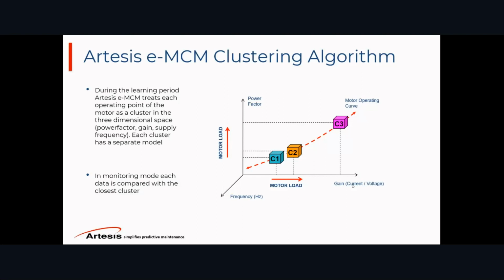If it's not an issue, and if it's a seasonal or intentional change in the system behavior, you can then update this model by just updating the software, and it will create additional clusters for that particular condition. That way you always ensure that all conditions are learned, and you're constantly comparing the actual process with what has been learned. If you see any deviation in between, then that will yield early indications about an incipient fault.